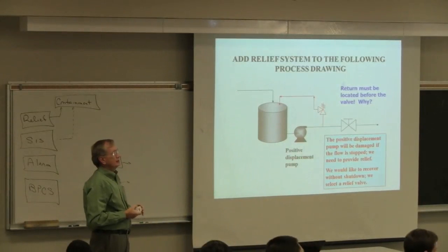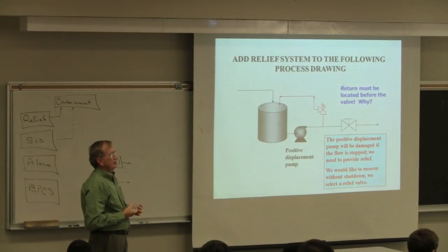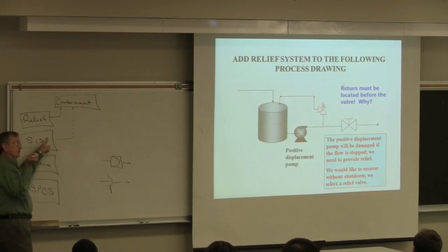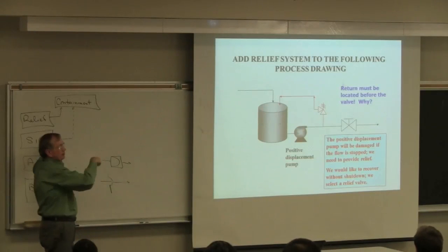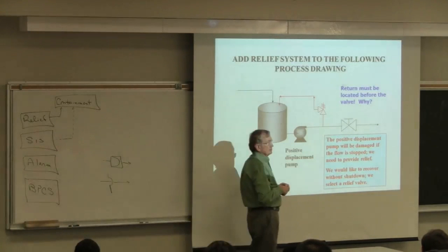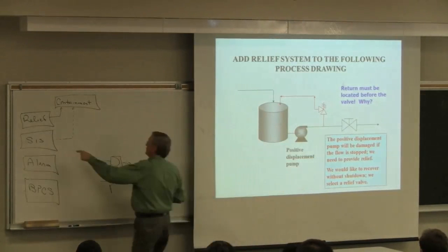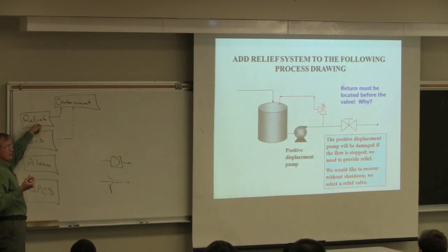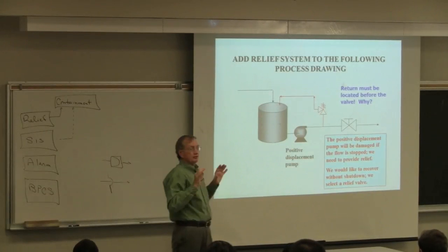A student asks: when is it not appropriate to use a digital safety system—like a high pressure switch that cuts power to the pump? That approach is at the SIS level. But a high pressure switch is a mechanical device that can fail, so you still need the mechanical relief layer below it. The pipe can be sized to handle the pressure without breaking, but the pump itself will be damaged. So you still need that last layer of relief protection.